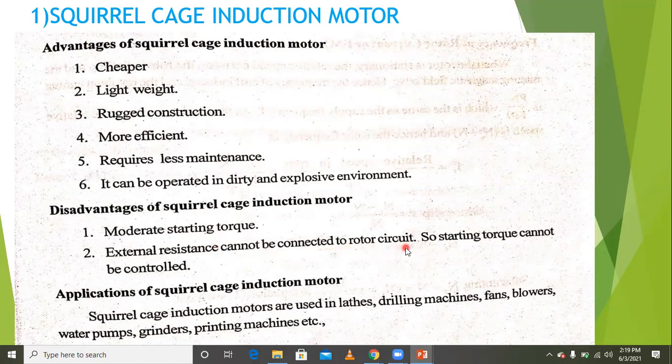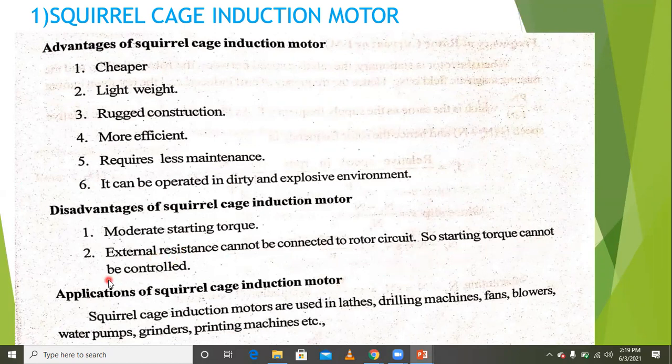The squirrel cage rotor is already short-circuited with end rings, so external resistance is not possible to connect to the rotor circuit. Since the rotor is internally short-circuited by end rings, starting torque cannot be controlled in the squirrel cage induction motor.